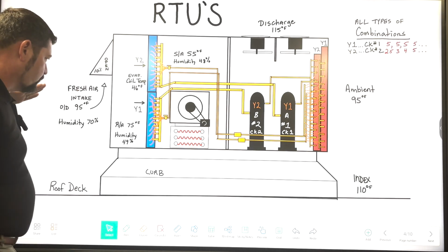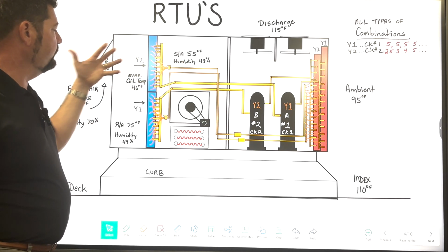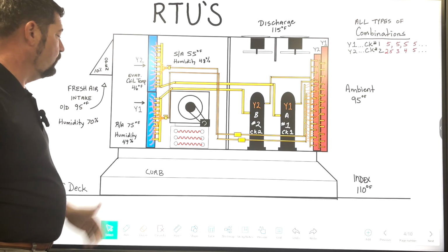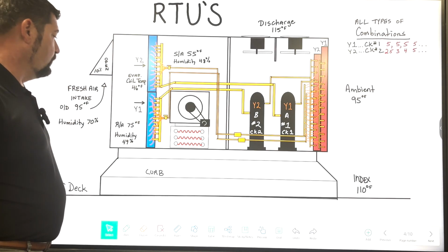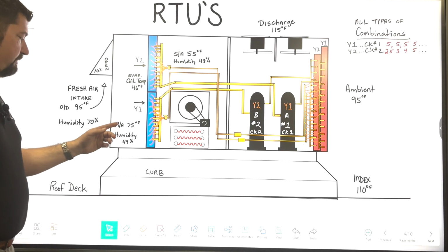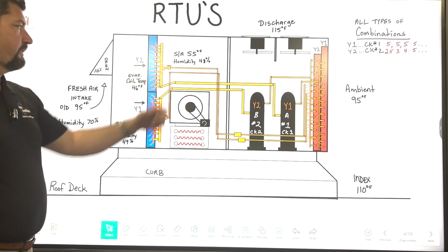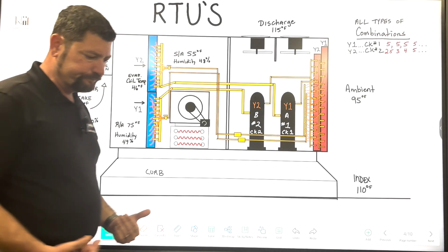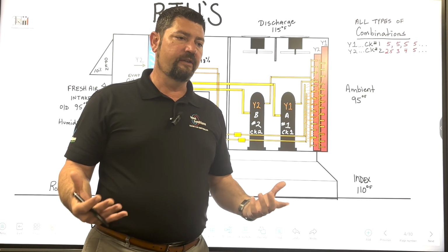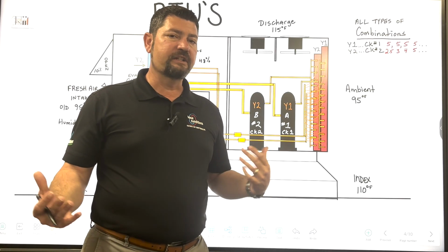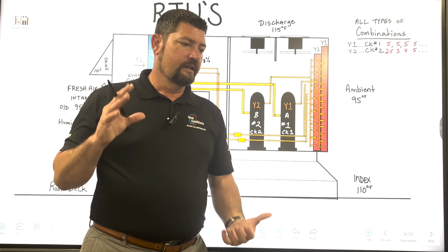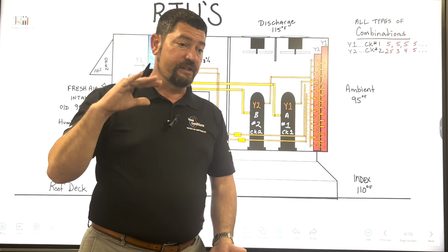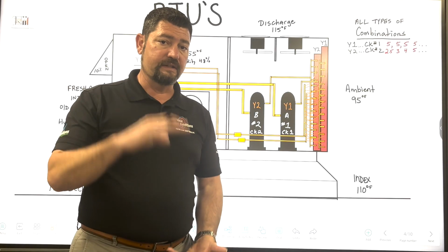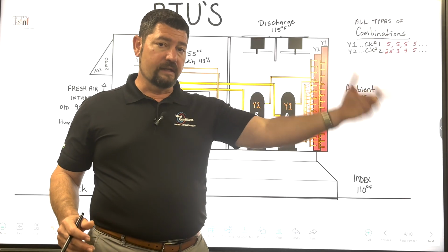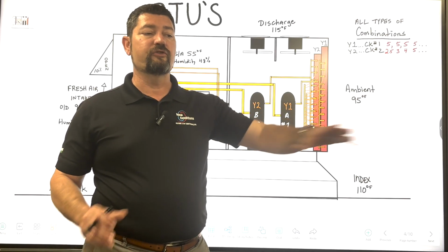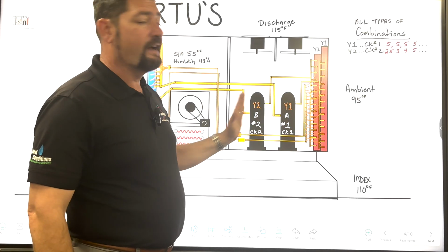So here you're controlling that air to move across a cold evaporator coil, which I just put up here as an example, 46-degree coil. Any humidity going across a cold coil is going to sweat. Now, if you look at my humidity here at 49% and my humidity here at 48%, it's not a dehumidifier. It is not here to remove a bunch of moisture. It is there to remove heat. These things are not spec'd out to run and dehumidify like these residential units that can actually stage themselves down as an inverter compressor naturally does. As it unloads, it runs longer and it targets that comfort that you're looking for by removing that moisture through length of run time. These units don't have that technology.